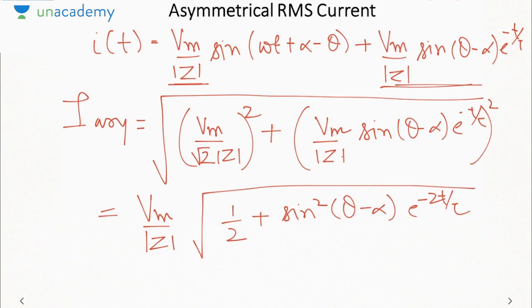Okay. Now if we observe, the current decays when we go from subtransient towards the steady state region, so the current is maximum in the subtransient region and minimum in the steady state. So where should we open the circuit breaker: in the subtransient, transient or the steady state? If we open in the subtransient region, current will be highest. Then what will be happening? We won't be able to extend the arc that will be formed due to that high current. So we cannot open the circuit breaker in the subtransient region because the arc will be too dangerous. Then we cannot open in the steady state region either, because steady state occurs after a long time. If fault current is allowed to persist for such a long duration, it can lead to system damage, because high current flowing for a long duration will cause overheating of the system. That means we have to operate in the transient region. So circuit breakers are always opened in the transient region, not in the subtransient or steady state.